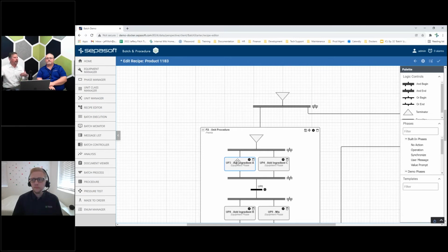So we say add this amount, go ahead and start, and it comes back and says I'm running. And you can do other things. You can say, hey, hold or pause. It'll come back and say, I'm pausing. Okay, now restart. All these kinds of commands are all part of the ISA 88 specification. And in that case, that communicates with the controller.